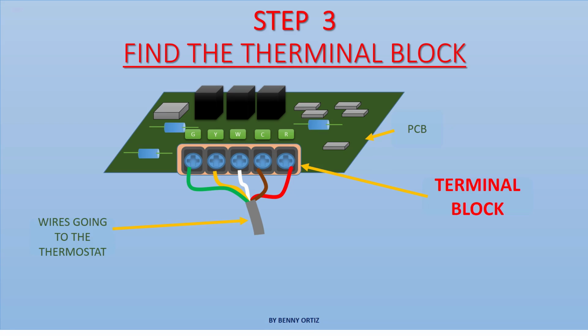For rooftop units, there is always a C terminal on the terminal block. Once this is verified, turn off the power again and start the installation. For a rooftop unit, the power on-off box is at the rooftop unit, so there is no need to go to the main electrical panel. For older air handler units using wire nut connections, locate the 24 volts AC transformer and trace the two low voltage wires to make sure one of them is connected to the red wires. In this case, the other wire from the transformer is the common wire.